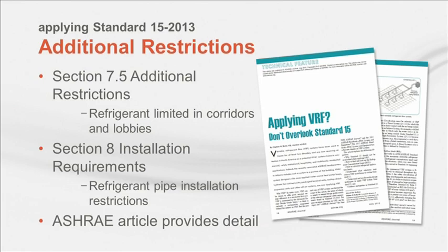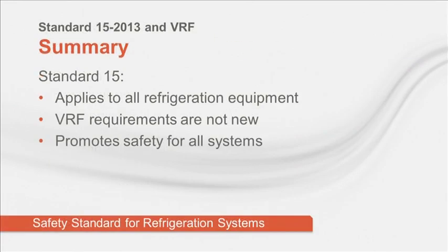apply to VRF systems. In summary, Standard 15 applies to all types of refrigeration equipment and all refrigerants. The main difference with VRF systems is the potential for higher refrigerant concentrations in the occupied spaces. If you understand and follow the requirements of Standard 15, VRF systems will be just as safe as any other refrigeration system. The next topic is complying with energy codes.